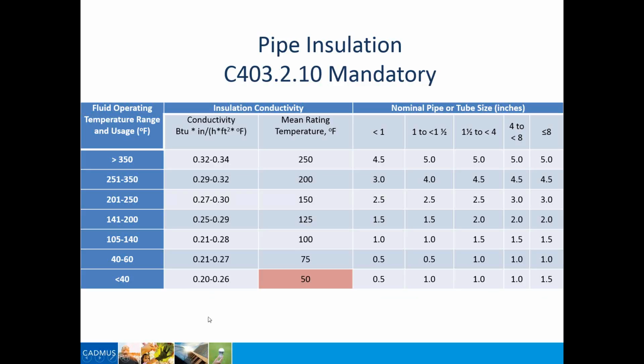So if I had a small, let's say a 5-ton cooling system, for example, maybe I've got less than a 1-inch line running from that to the evaporator coil. I'd have to put a half inch of insulation on your refrigerant line, and this is only for that line. The requirements really haven't changed on what line you have to insulate. So if the fluid temperature is between 40 and 60 degrees in that particular line, then you have to put on a half inch of insulation.